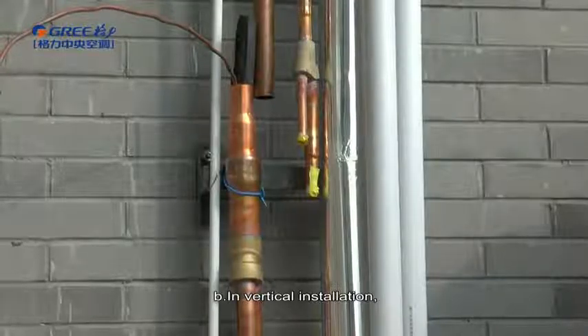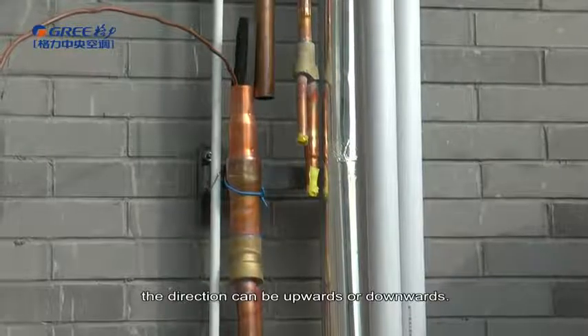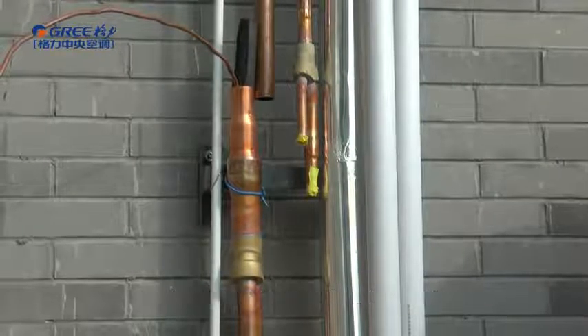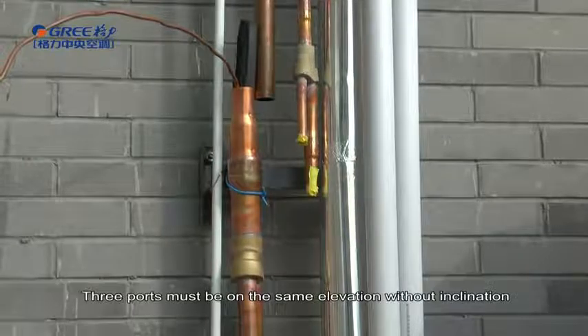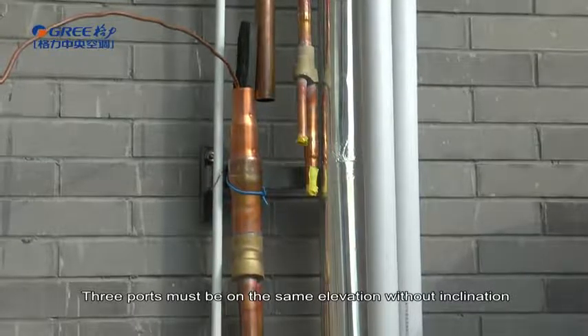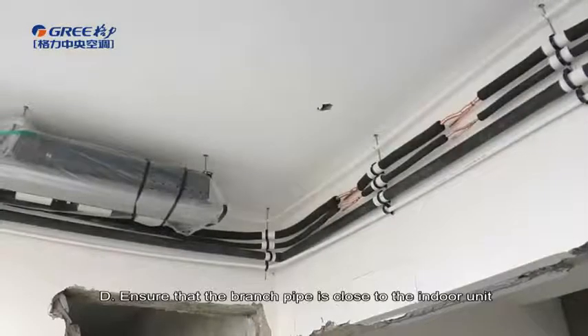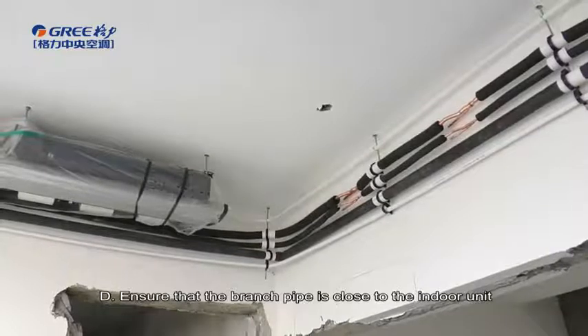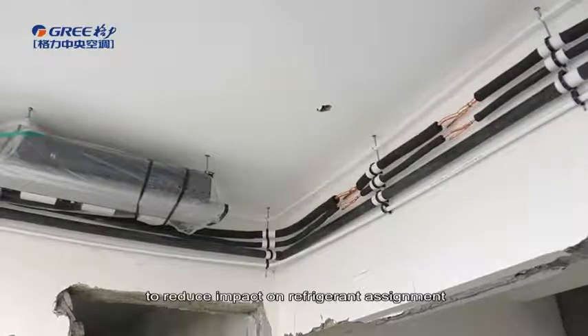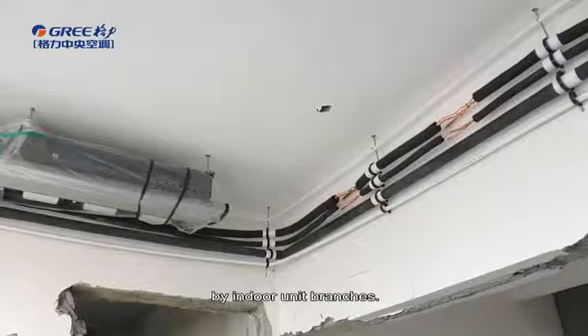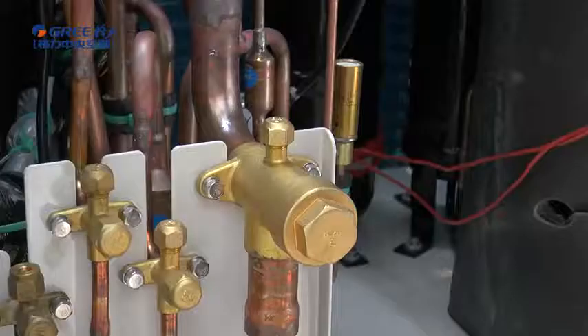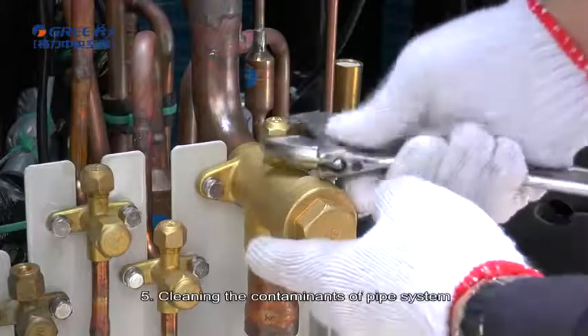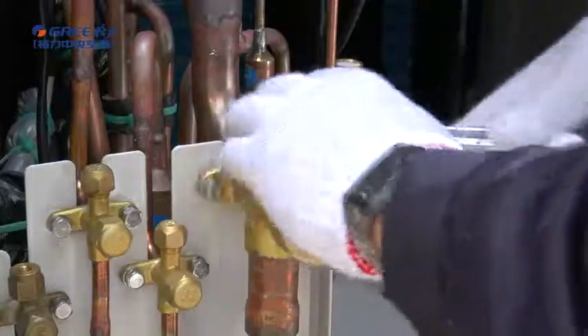B. In vertical installation, the direction can be upwards or downwards. 3 ports must be on the same elevation without inclination. D. Ensure that the branch pipe is close to the indoor unit to reduce impact on refrigerant assignment by indoor unit branches. Fifth, cleaning the contaminants of pipe system.